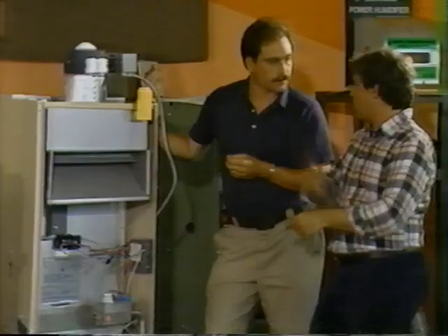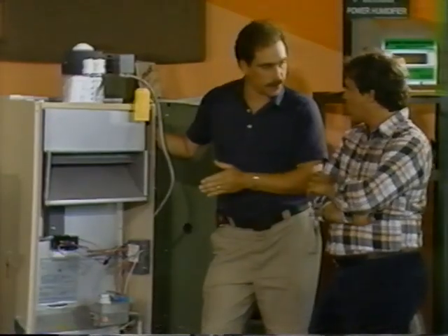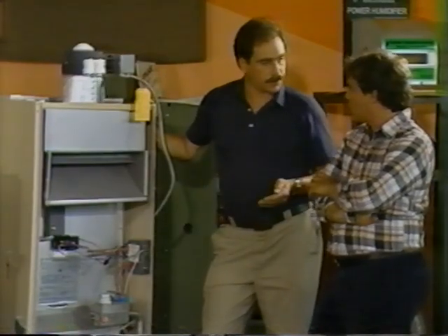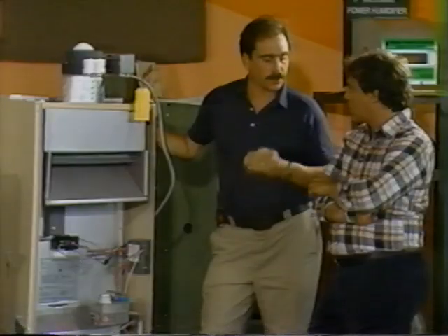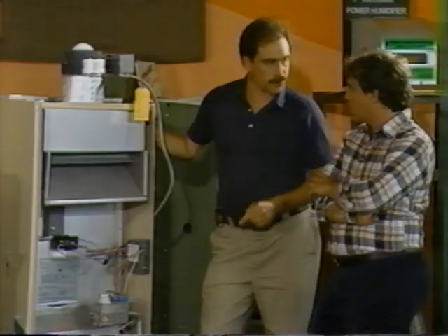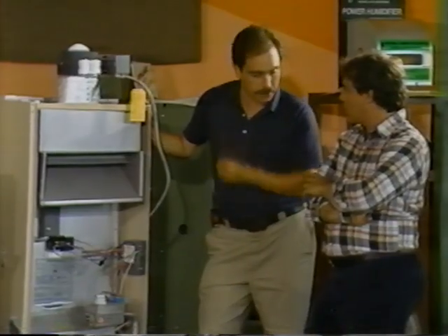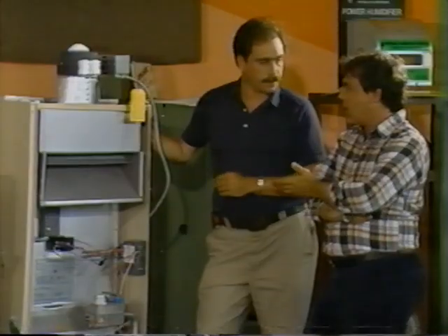They're hot, they go up. Exactly. And the problem with it is that if other exhaust equipment is turned on in an energy-conserving building, it is possible to reverse the flue in this unit and bring combustion products into the home. How would that happen? If you turned on, for example, a Jenn-Air. Absolutely no place in an energy-conserving house.